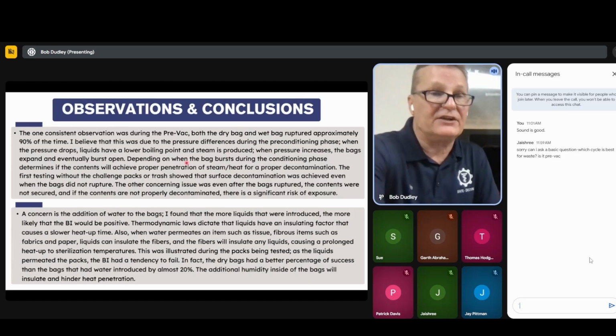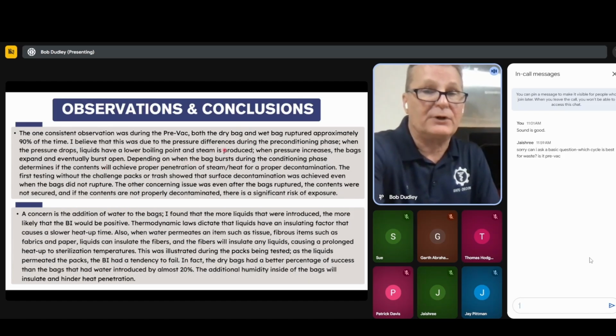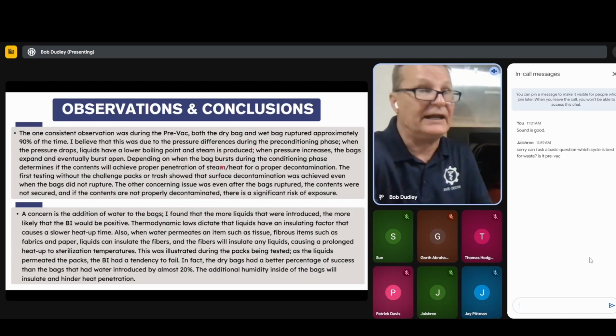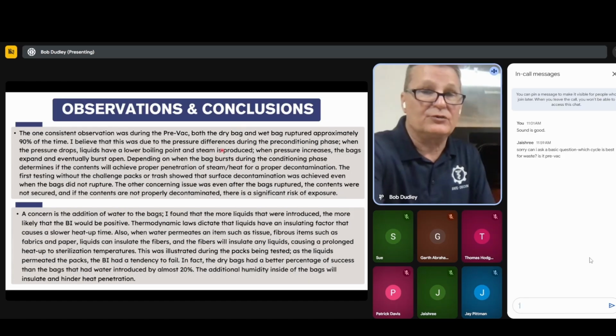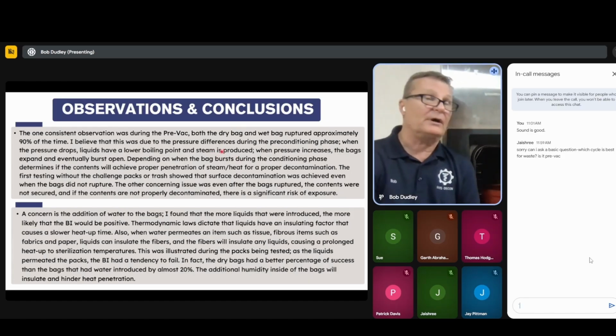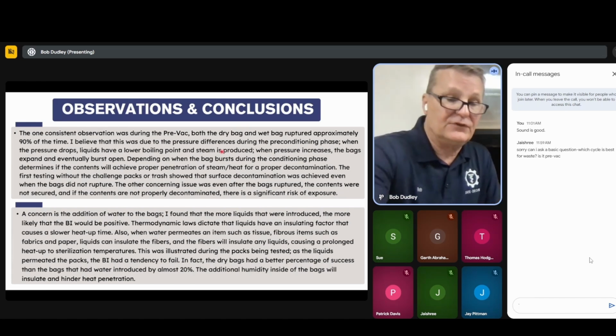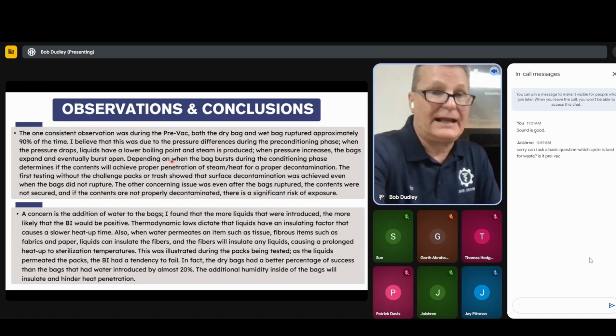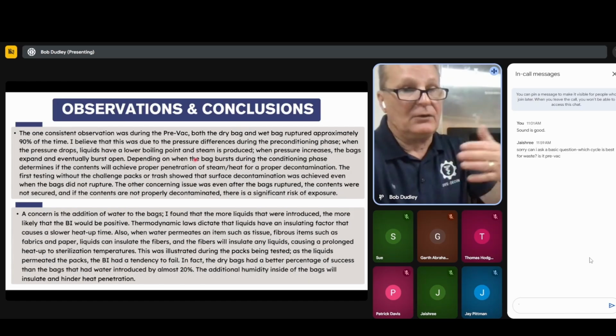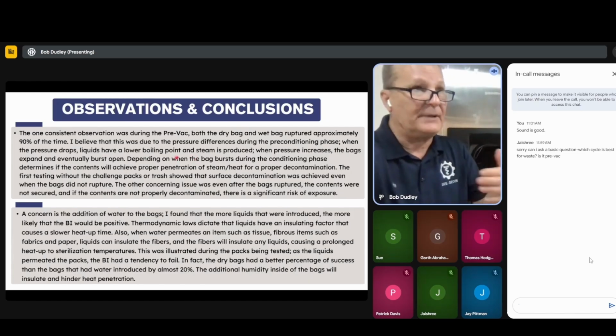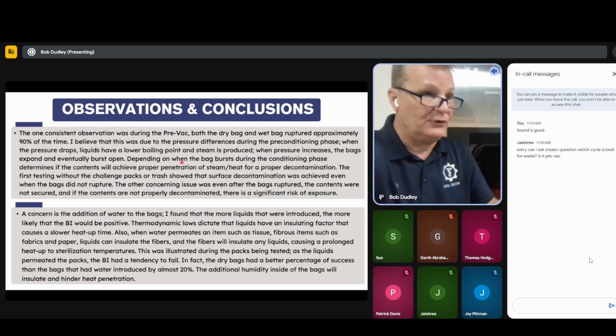I believe that it's pretty much due to the pressure differences in the preconditioning phase. This is one of the reasons why everywhere I went, they would have the standard three preconditioning pulses, and I increased it to 4 to give, if you don't have the Safe-Decon unit, what this does is it gives the bags a longer opportunity to try and get busted open.